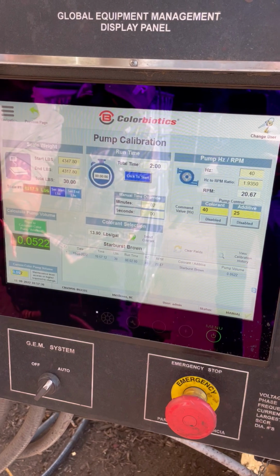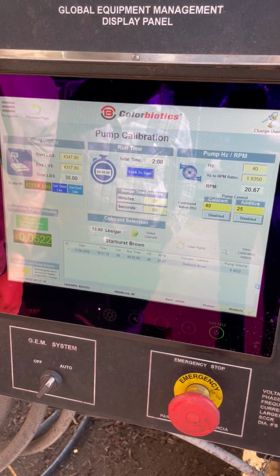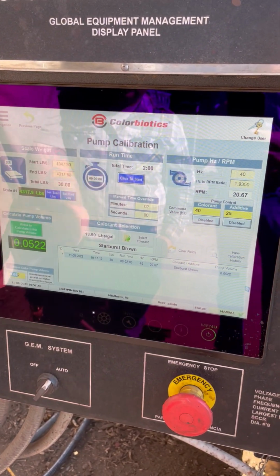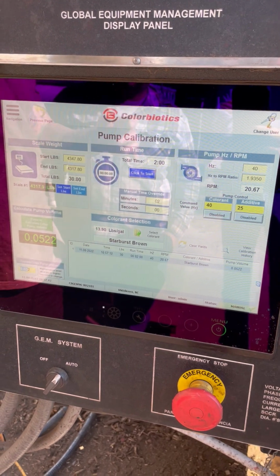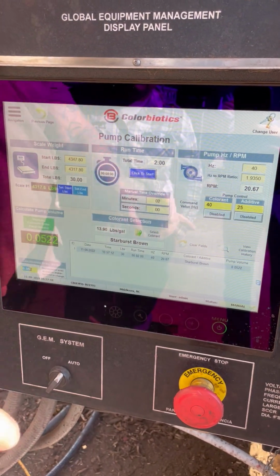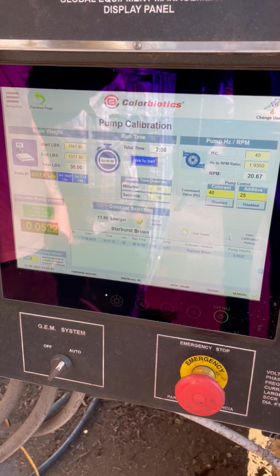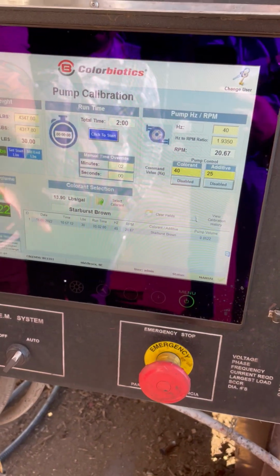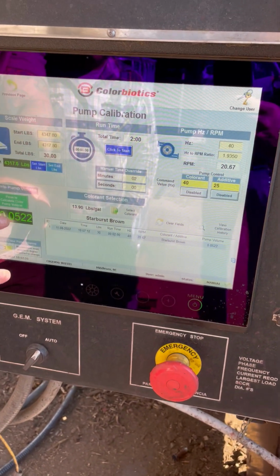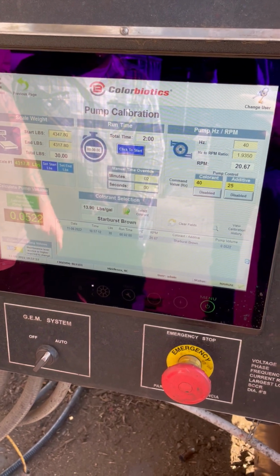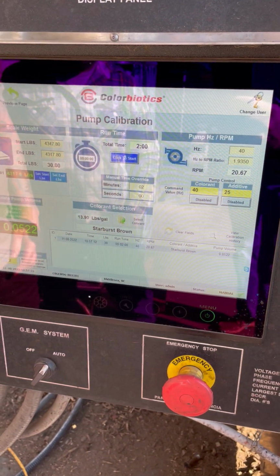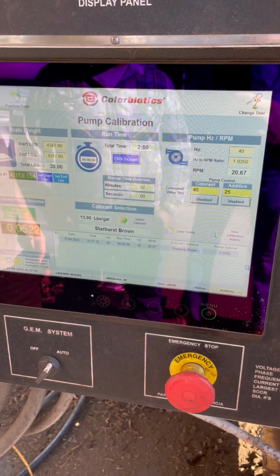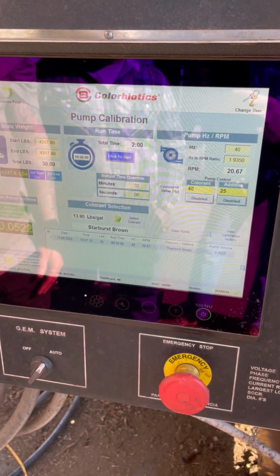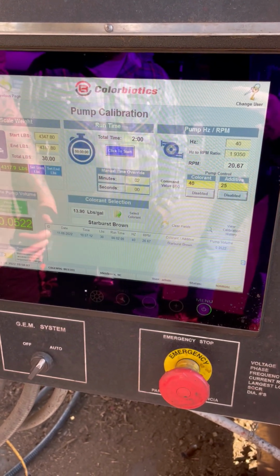So now our numbers are matched. What I do recommend when you guys start doing this is do at least 3 of them in different hertz settings, like a low, medium, and high, and then obviously you'll get an average. They might not always come up to 0.052 because it all depends on when you hit that on the time. It might be 0.051 next time, 0.053 next time, but just go in the middle and you're pretty much calibrated.